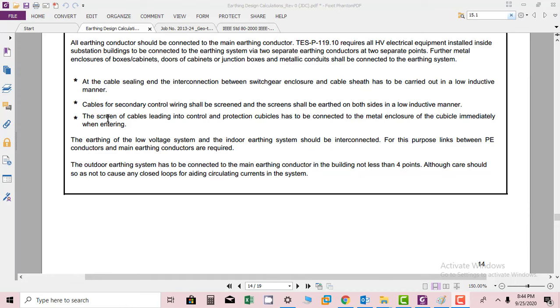The screen of cable feeding into controller protection cubicle has to be connected to the metal enclosure of the cubicle immediately. The earthing of low voltage system and the indoor earthing system should be interconnected. For this purpose, links between PE conductors are required.